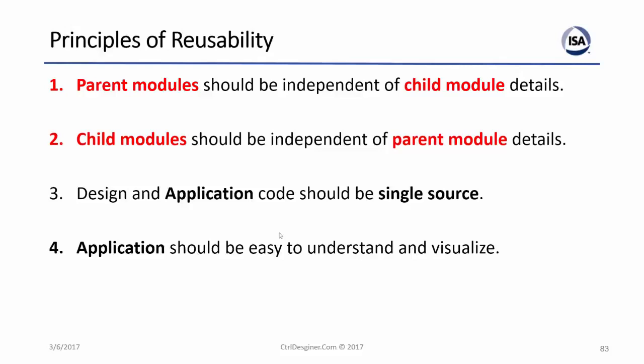At the same time, the child module should be independent of the parent module. The child module internally should not look at the temperature of the distillation tower or the level, and should just communicate with the master in a very specific way. Otherwise, you need to make sure operators understand how we go from one to another and what the mode of communication is. There is no internal communication, because that becomes very confusing. The application should be single source, and easy to understand and visualize.